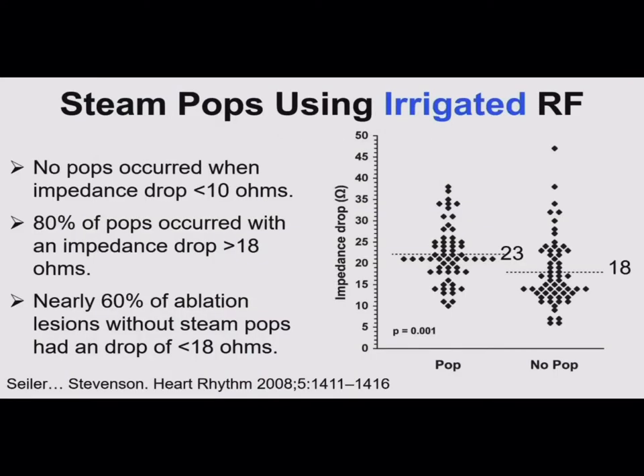From a Bill Stevenson paper on steam pops with irrigated RF: when he kept the impedance drop to less than 10 ohms, they never had a steam pop. Over 18 ohms, about 80% steam pop rate. So I try to keep it for the ventricle 10 to 12 ohms. If you're getting a big drop hitting 18 to 20 ohms, that's where you come off or start backing off on the power. Usually start at 25 to 30 watts and ramp up while keeping an eye on the impedance.